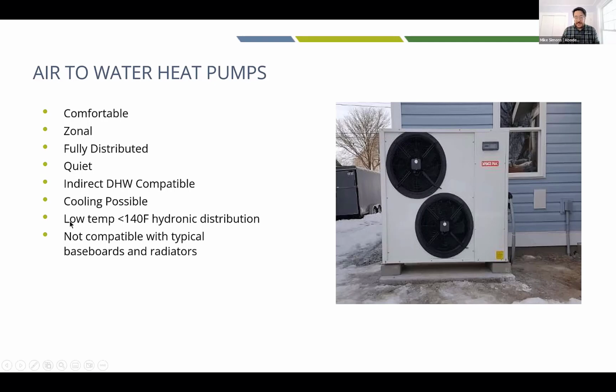The big reason these aren't everywhere is that the temperature they put out isn't 180 degrees like your baseboards may need, or 212 degrees like your steam radiators may need. At its highest it's around 140 degrees, but even 140 degree water isn't the best performance range for this equipment—that's more like 90 to 120 degree water. So for the vast majority of homes, you can't just rip out your boiler and put in an air-to-water heat pump system.